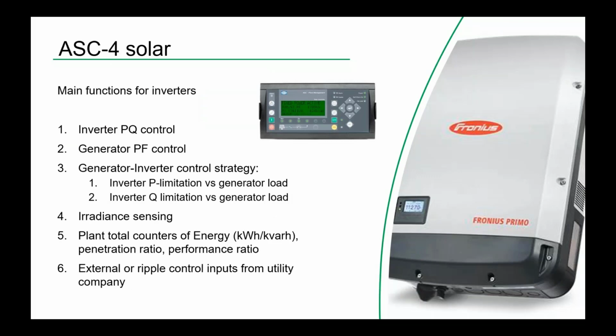If we look at the inverters, one ASC controller, usually we say it can control 32 inverters. This is because you have a Modbus line, and typically the Modbus limitation is 32, but there are ways to overcome that. Just as a general rule of thumb, 32 inverters per ASC. The P and Q control is of course the most important functionality that we have. We need to control the curtailment in order to control the set point of the plant. At the same time, we have the generator power factor control. We'll see later how we do all these things.